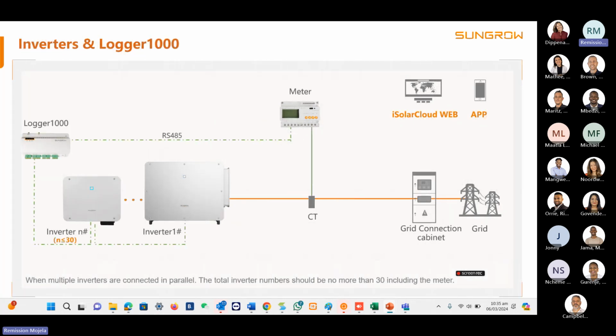The next part is the inverter and the Logger 1000. One important thing is that with our devices, you can connect up to 30, including the meter, but the important thing to note is that it doesn't matter what the size of the inverter is. You can mix and match with all our devices. You can use a 33, a 110, 120, and 125 and a 50 on site. As long as you have the Logger 1000, it will be able to send the right set points to each and every inverter, because it sends set points in percentage depending on the amount of power that is required from the grid side. So basically, it doesn't matter which device it is. As long as you have them, you can mix and match. It will work just fine.